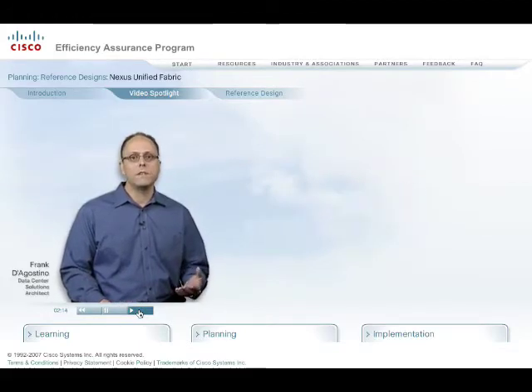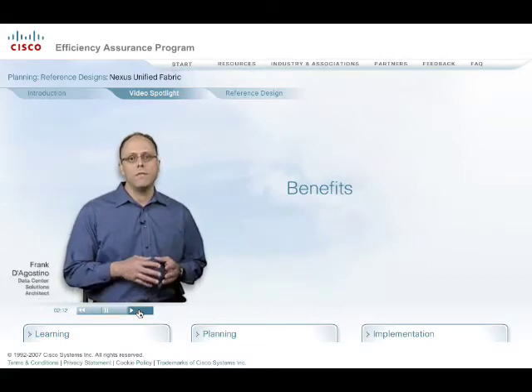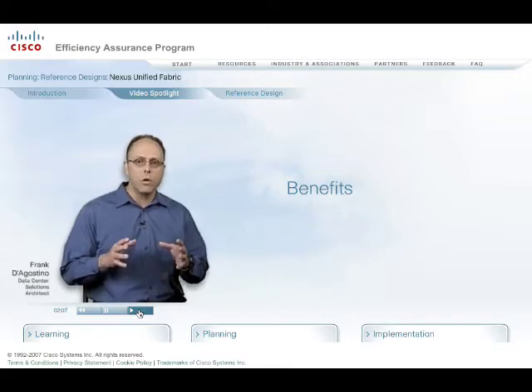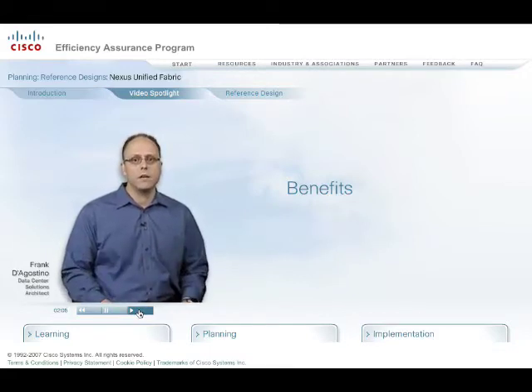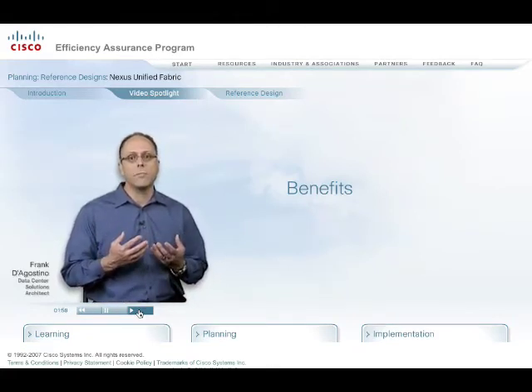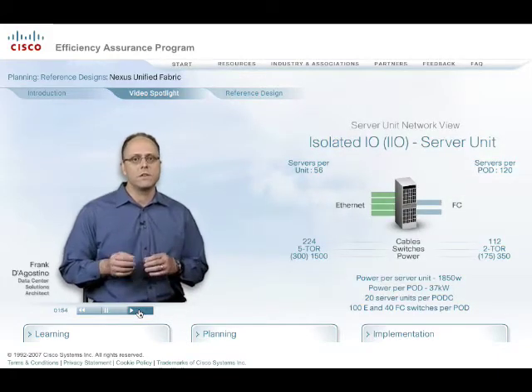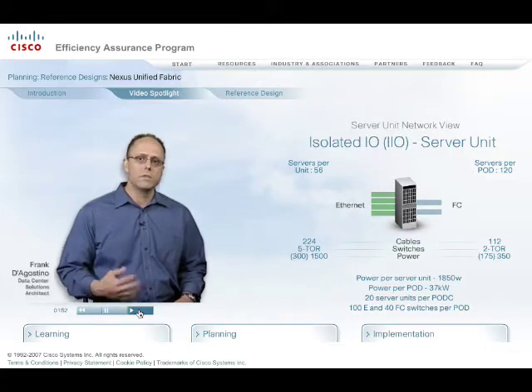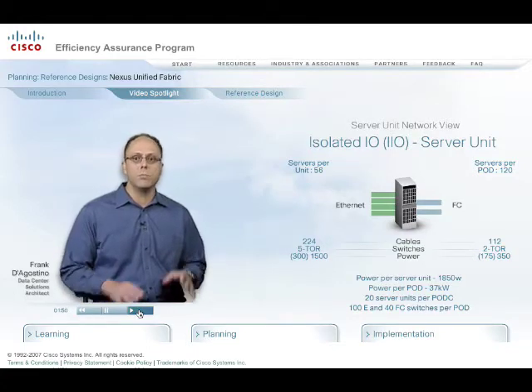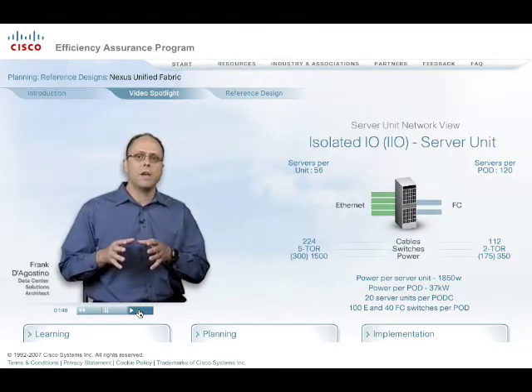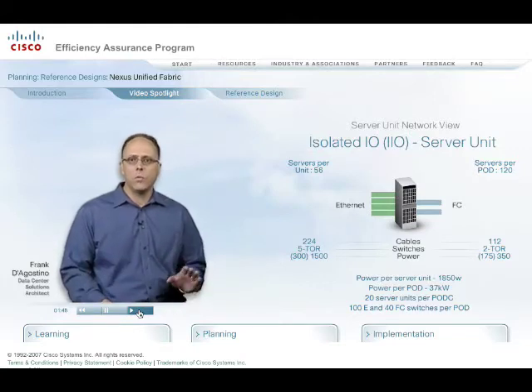The benefits derived from implementing unified fabrics with the Nexus family include an immediate efficiency gain in reducing the total cable count in the data center, which may improve air distribution assuming a raised floor installation. In terms of unified fabrics' impact on the server domain, there is an efficiency gain potential in reducing connections to the server. A typical virtualized server configuration requires multiple NICs and HBAs that will consume 20 to 35 watts while utilizing six to eight connections on average.